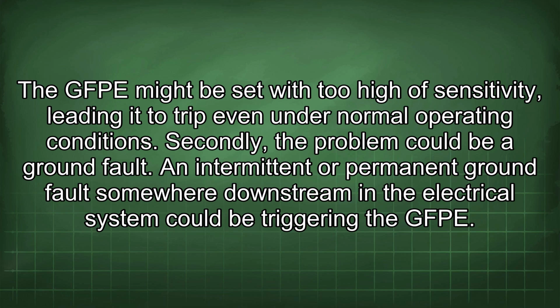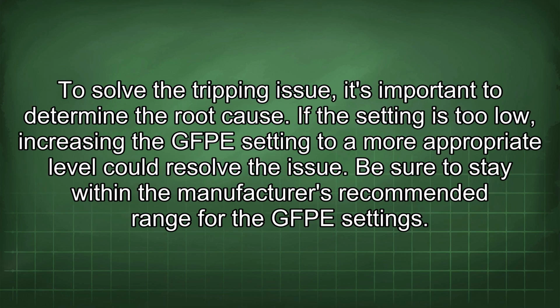Secondly, the problem could be a ground fault. An intermittent or permanent ground fault somewhere downstream in the electrical system could be triggering the GFPE. To solve the tripping issue, it's important to determine the root cause. If the setting is too low, increasing the GFPE setting to a more appropriate level could resolve the issue. Be sure to stay within the manufacturer's recommended range for the GFPE settings.